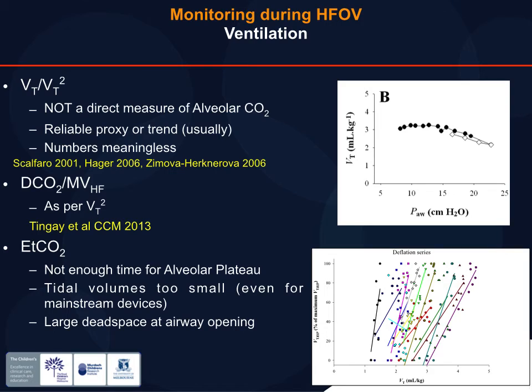So what about directly measuring tidal volume? Because of the way gas is moving in the lungs, this is not a direct measure of absolute tidal volume at an alveolar level. They essentially will be a proxy again, and some of that will be based around the algorithm of how tidal volume is measured, the accuracy of your device, and the frequency that the device is being used at. So there's very little data that actually validates the flow sensors in our devices on high frequency mode to reliably measure tidal volume. And that data that does exist has only been done at higher frequencies above 8. So at lower frequencies, we're not quite sure. Probably it is not quite as important what the absolute number is, but again, it will depend on the trend.